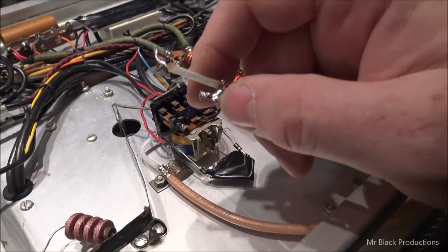This is an oil-based substance that does not hold up for shit. This neoprene in here is garbage. You really start putting some pressure on this wire, and that center conductor is going to heat up this plastic, and it's going to migrate through the plastic and short against the shield, hence causing our failure.